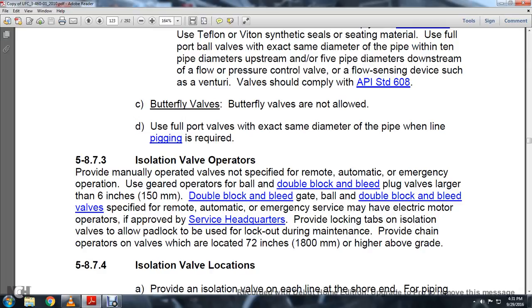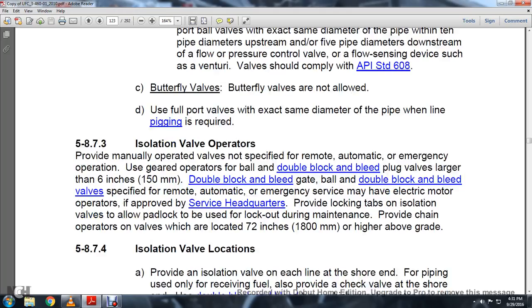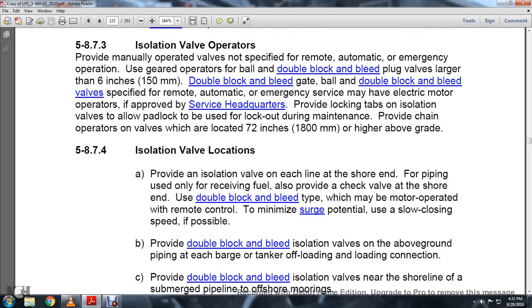5873, isolation valve operators. Provide a manually operated valve, with gear operation for the non-specified remote automatic emergency operation of ball valves, double block and bleed plug valves larger than 6 inches, and double block and bleed gate and ball valves. Double block and bleed valves specified with remote automatic emergency service may have electric motor operators if appropriate. Provide locking tabs on the isolation valve to allow a padlock to be used for lockout during maintenance. Provide chain operators on valves located more than 72 inches above grade.